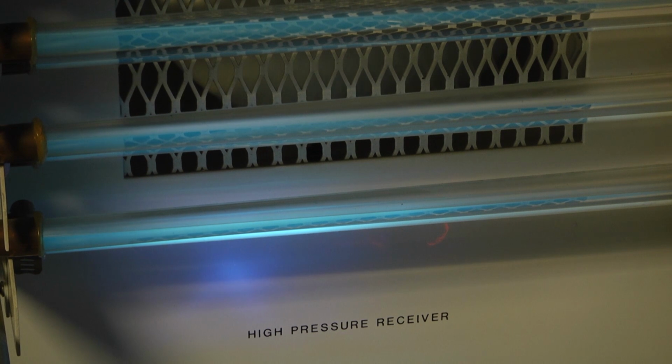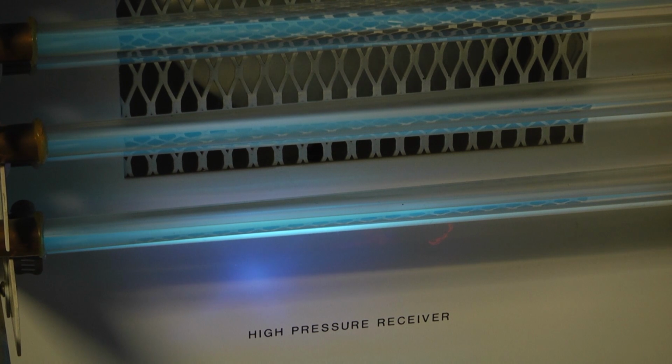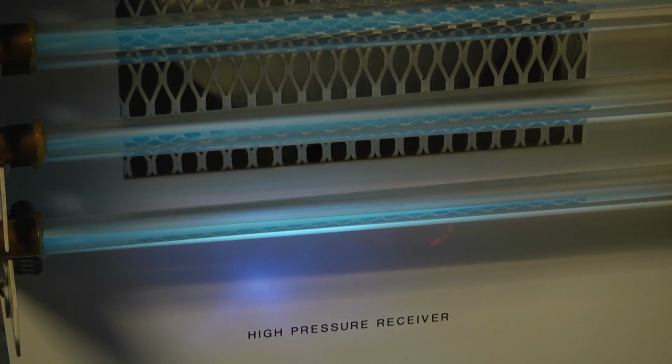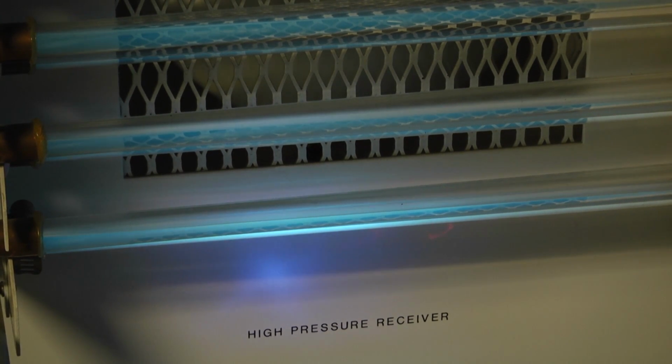It's really not an effective method of heat transfer. The most effective way to transfer heat is by changing the state of the refrigerant. However, by subcooling it, we are guaranteeing that the liquid refrigerant that travels back to the metering device to start this process all over again is 100% liquid refrigerant below its condensing point. Now, the metering device will quickly drop the pressure and the saturation temperature, feed refrigerant back to the evaporator, and the process will continue over and over again.